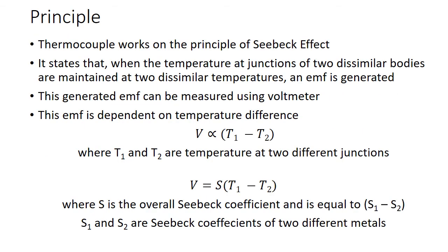So now we will move on to the principle of thermocouple. This thermocouple works on the principle of Seebeck effect. Whenever the two dissimilar bodies of the thermocouple are joined together, we will have two junctions, right? The Seebeck effect states that when the two junctions are maintained at two different temperatures, an EMF is generated within that loop. This generated EMF can be measured using a voltmeter, right?